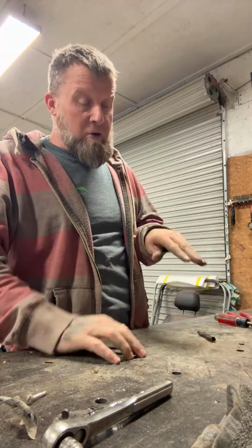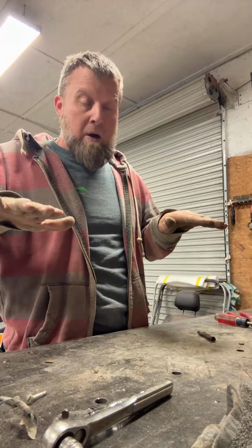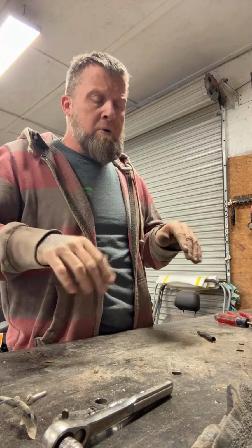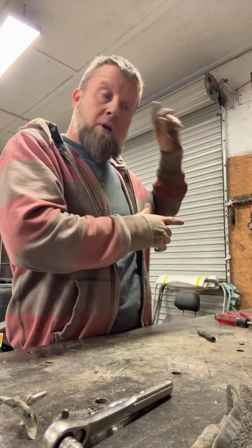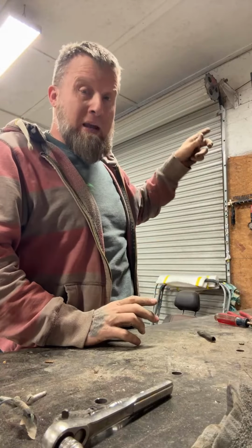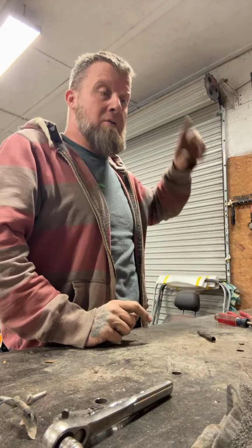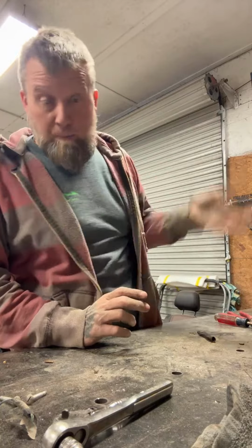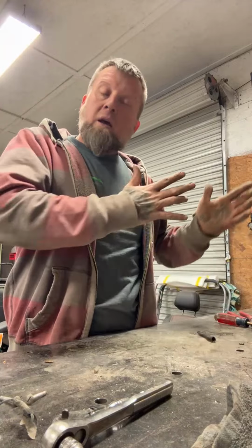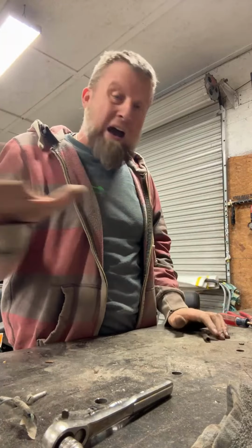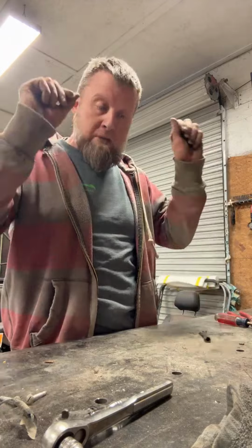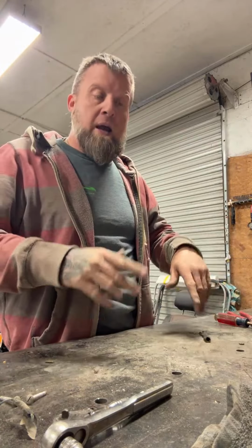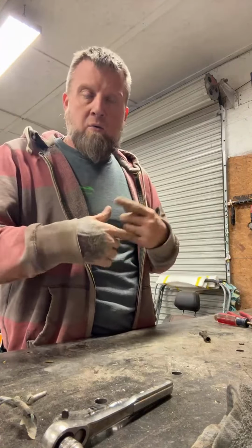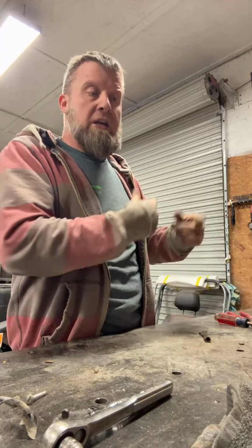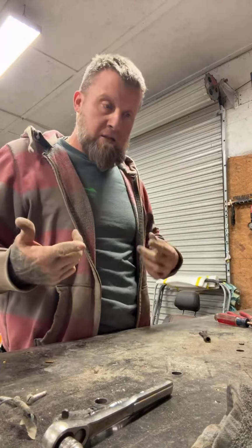So you got the first one, the second one, the third one, they all come on. Once they come on, they're heating up the air super fast. The blower motor knows, hey, we got all 3 elements on, we got to get to work. So the little fan comes on and it just supercharges all the air as fast as it can for like 5 minutes. And then what happens, everything cuts off, everything cools down, and it keeps doing this cycle until it achieves the heat that you're asking for.